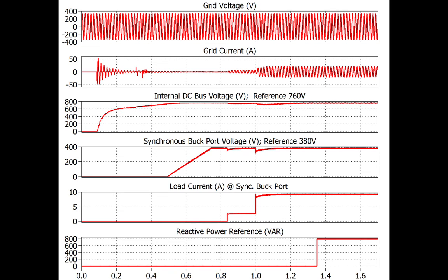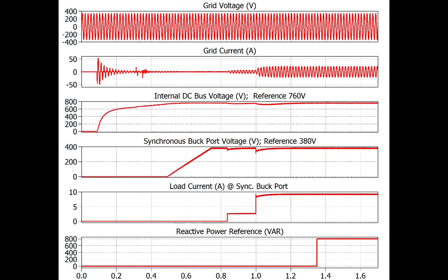Two cycles later, the controller starts the synchronous buck converter and increases its voltage reference as a ramp from 0 to 380 volts. Up until now, the load relays have been open, meaning they didn't have any voltage across them. This changes once the voltage across the buck filter capacitor is stabilized and the load then sees the 380 volts.